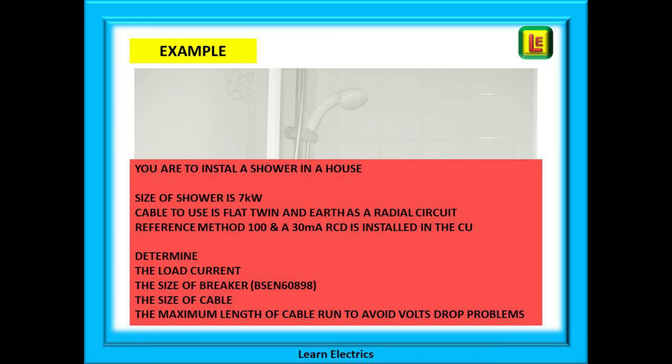We need to calculate the design or load current, then decide the size of breaker to use — we will use a standard BS EN 60898 breaker type B. Having done that we can select the correct size cable from the appropriate tables, and then determine the maximum length of cable run to ensure we do not exceed it.